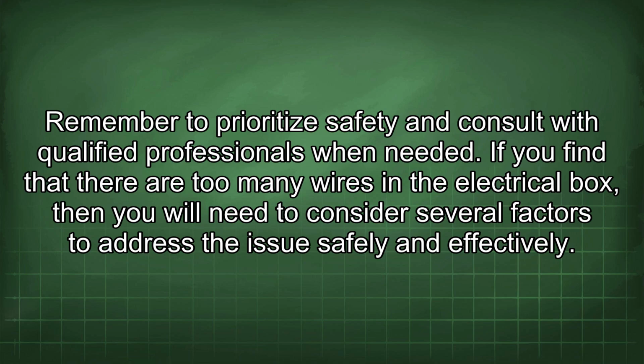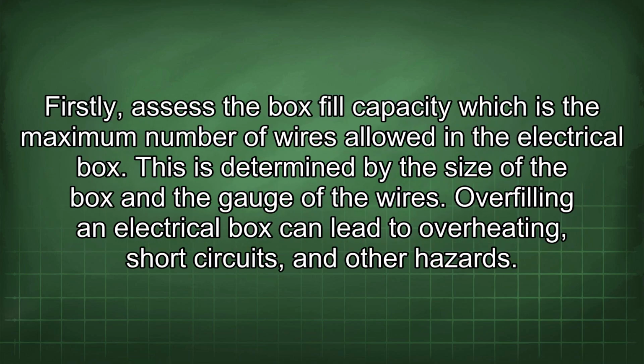If you find that there are too many wires in the electrical box, then you will need to consider several factors to address the issue safely and effectively. Firstly, assess the box fill capacity, which is the maximum number of wires allowed in the electrical box. This is determined by the size of the box and the gauge of the wires. Overfilling an electrical box can lead to overheating, short circuits, and other hazards.